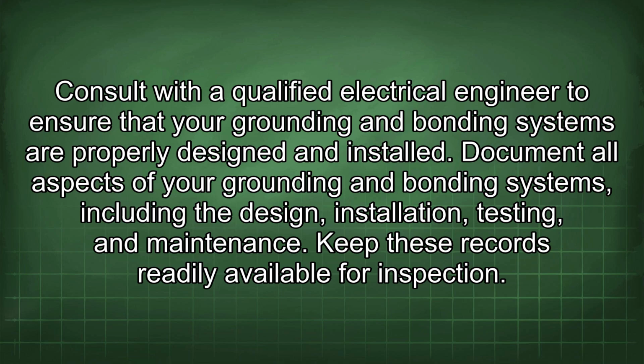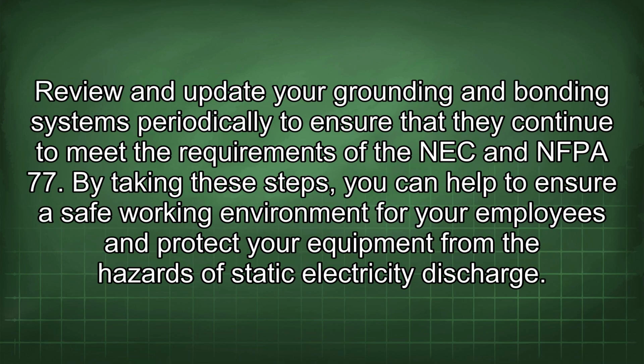Document all aspects of your grounding and bonding systems, including the design, installation, testing, and maintenance. Keep these records readily available for inspection. Review and update your grounding and bonding systems periodically to ensure that they continue to meet the requirements of the NEC and NFPA 77. By taking these steps, you can help to ensure a safe working environment for your employees and protect your equipment from the hazards of static electricity discharge.